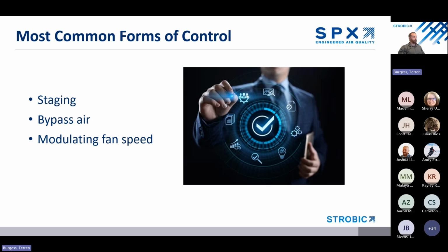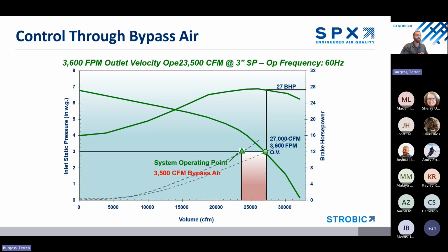So we've got a few ways in which control takes place: staging, bypass air, modulation of fan speed. Just to give some backstory, in a lot of traditional lab exhaust systems, right, these fans have a fixed speed and flow that they need to run at to stay stable and to keep the exhaust plume safely diluted. Now, the problem is the lab's actual demand often drops below that level. Maybe there are fewer fume hoods or certain spaces are not in use, right? And to deal with that mismatch in a constant speed setting, the system brings in or injects what's called bypass air. So basically, it's pulling in ambient air and mixing it with the exhaust stream so the fans can continue running at their set speed while concurrently not overpressurizing the space.